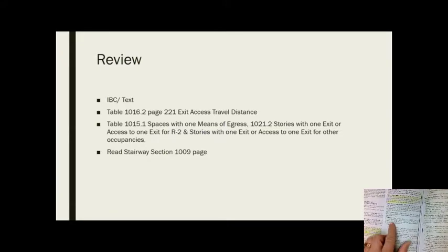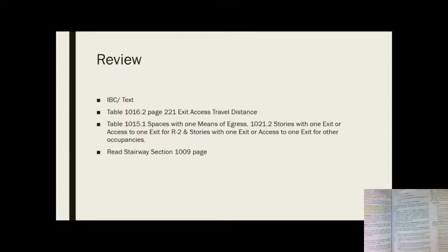It's also going to talk about doors. Doors, when fully open, should not reduce the required width by more than 7 inches. What it's talking about is your corridor. So if your hallway is opening, the door cannot intrude into that pathway, means of egress, more than 7 inches. You'll notice in our design building and a lot of different buildings, you see that the doorways are recessed within the classroom. That's what it's talking about. It tells you, of course, mounting, the hardware, all of the different items that go here.